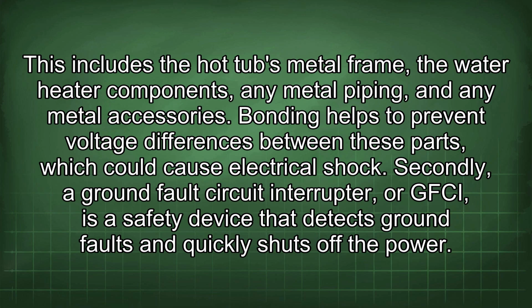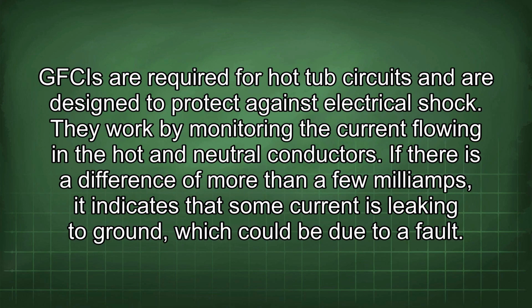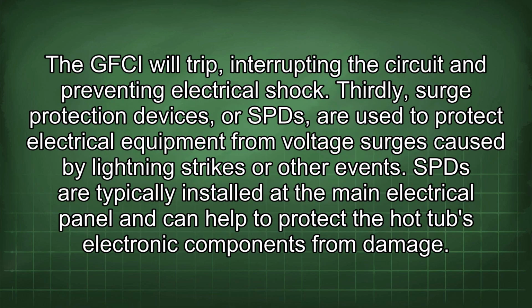Secondly, a ground fault circuit interrupter, or GFCI, is a safety device that detects ground faults and quickly shuts off the power. GFCIs are required for hot tub circuits and are designed to protect against electrical shock. They work by monitoring the current flowing in the hot and neutral conductors. If there is a difference of more than a few milliamps, it indicates that some current is leaking to ground, which could be due to a fault. The GFCI will trip, interrupting the circuit and preventing electrical shock.